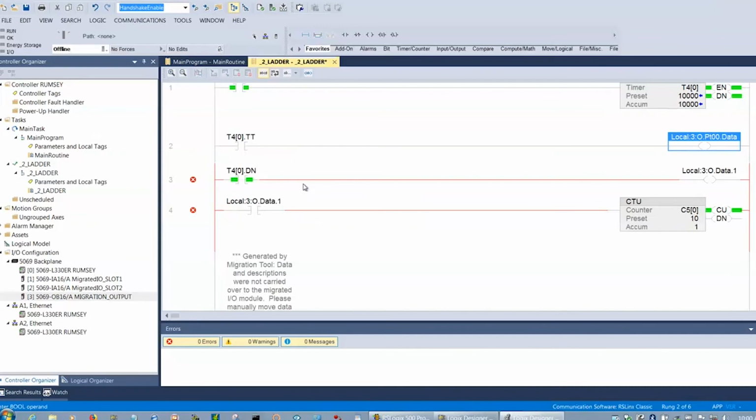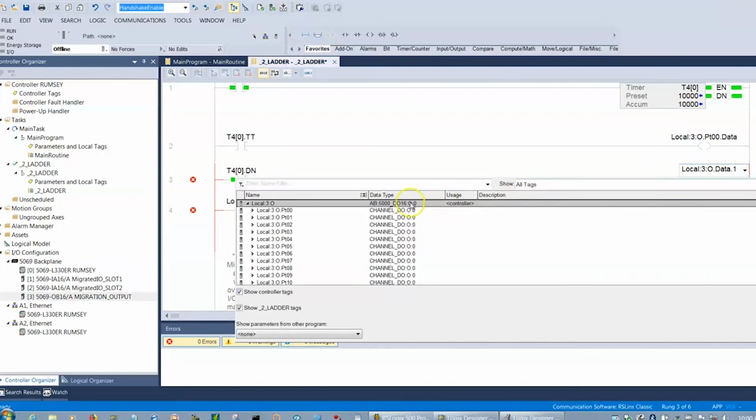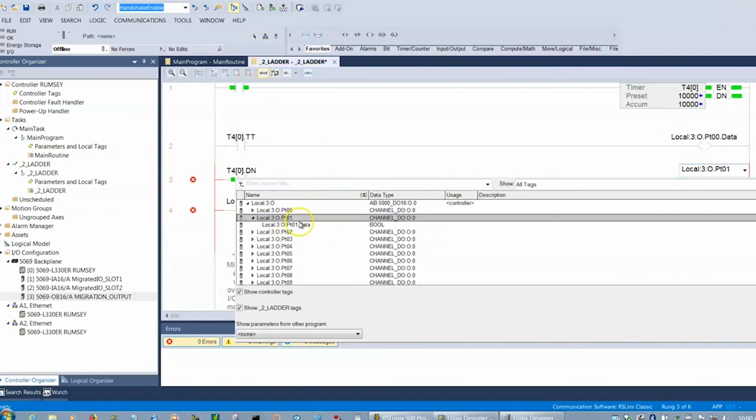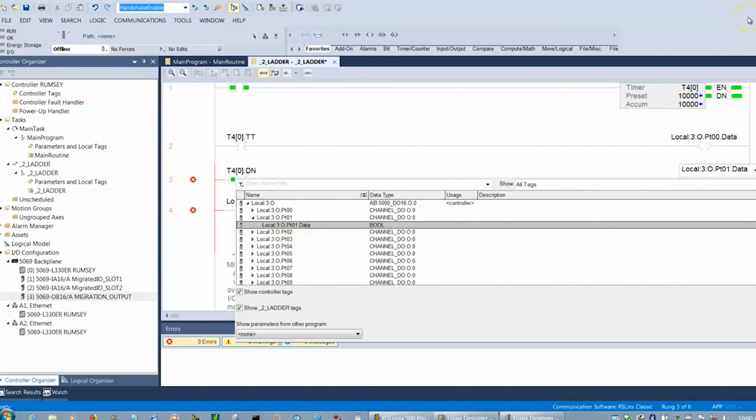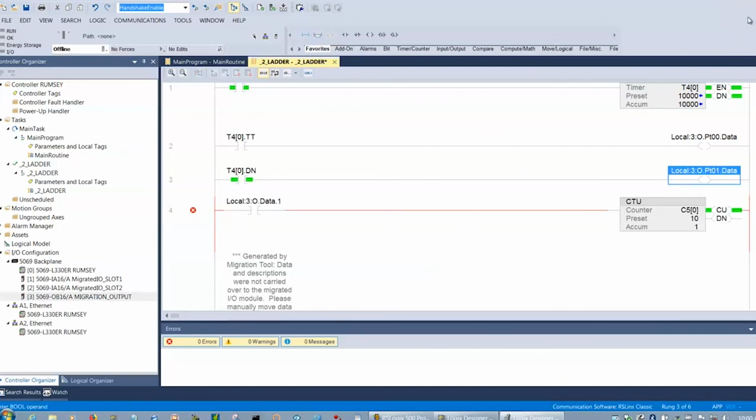And if you can notice here on rung 2, the error symbol went away. That's because this is now legal code. It would run in a processor. Let's do the next one. Double click, navigate down to the first, the second output technically, right? Enter, enter. As you can see, the errors went away again. Now this is, as you can see on the left on rung 4 in the beginning, the same address as the end of rung 3. So as I show in my classes, left click drag, and you have no more errors anymore.